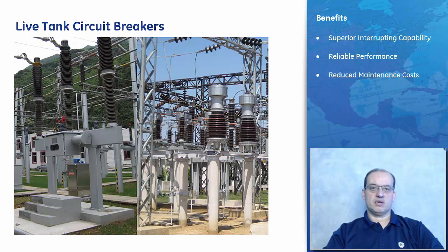The characteristics of the SF6 gas provide the live tank circuit breaker and associated components with a highly reliable insulating capability. The live tank breakers are designed with a leakage rate of less than 0.5% per year, which of course reduces the maintenance and cost of maintenance. They have been engineered to minimize the inspection and maintenance requirement, and are designed with a spring operating mechanism to further reduce the maintenance cost and lower the overall cost of ownership.